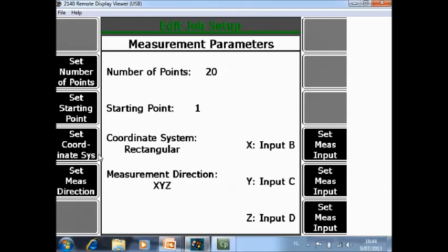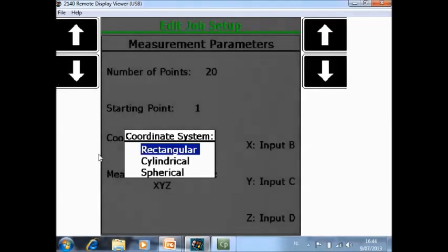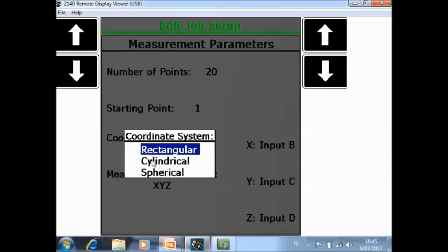Your starting point is where your reference sensor will be installed. And set coordinate system. There are three options. You can choose a rectangular, a cylindrical or a spherical coordinate system. But for most applications rectangular systems will be used. Cylindrical is for a tank and spherical is for a ball.